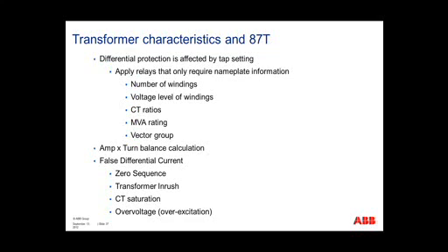So your differential protection is affected by the tap settings. Typically the best way to do it is to only use relays that require nameplate information from the transformer. The nameplate information includes your number of windings, your voltage level, your CT ratios, your MVA, and your vector group. With this information, you can input the nameplate data into the microprocessor-based relay. It will then in turn calculate your turns balance equation. So you can set your CT ratios at any level you want to. The turns balance equation is calculated for you.